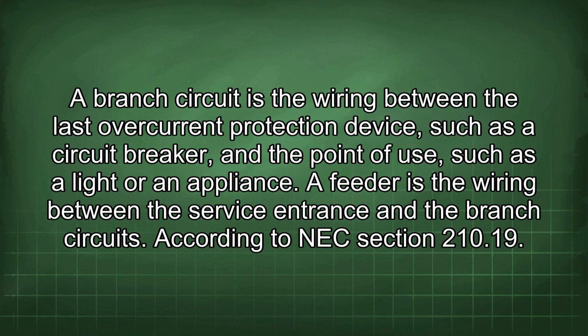A branch circuit is the wiring between the last overcurrent protection device, such as a circuit breaker, and the point of use, such as a light or an appliance. A feeder is the wiring between the service entrance and the branch circuits.